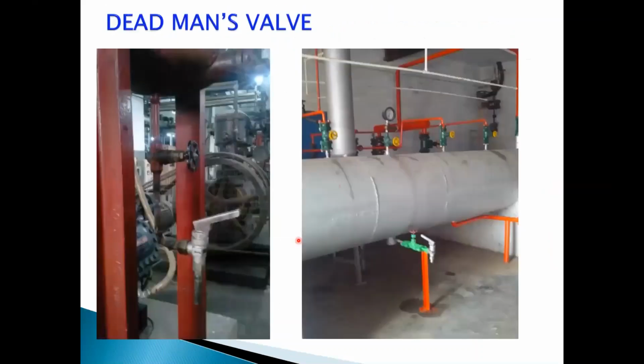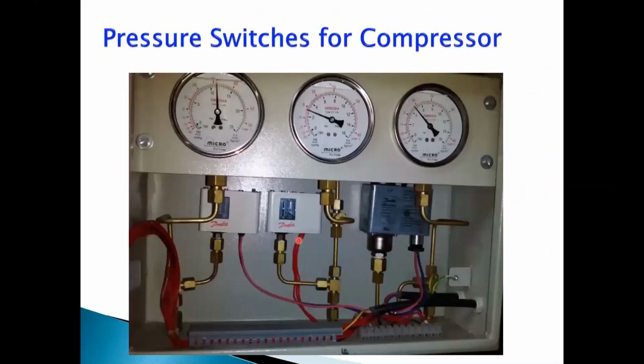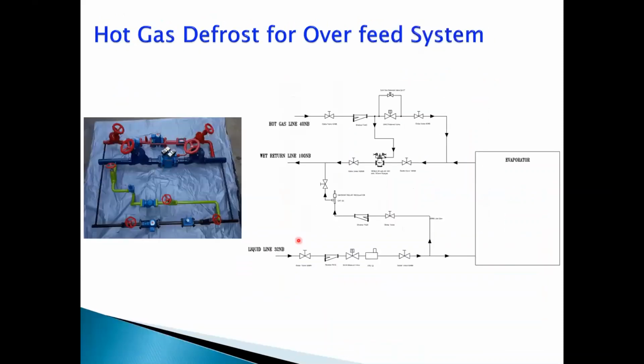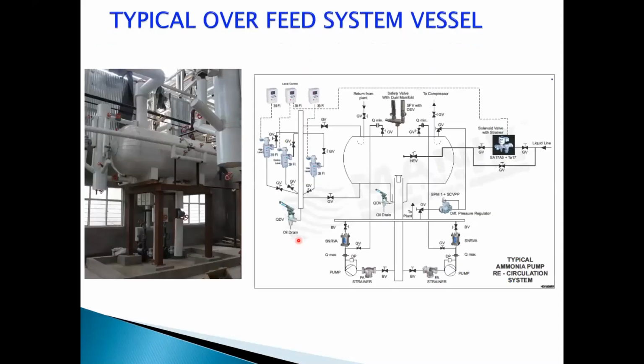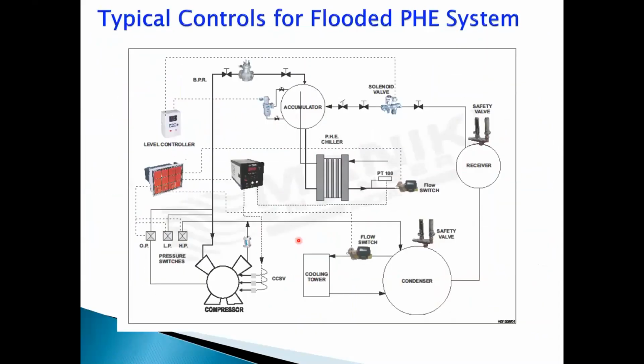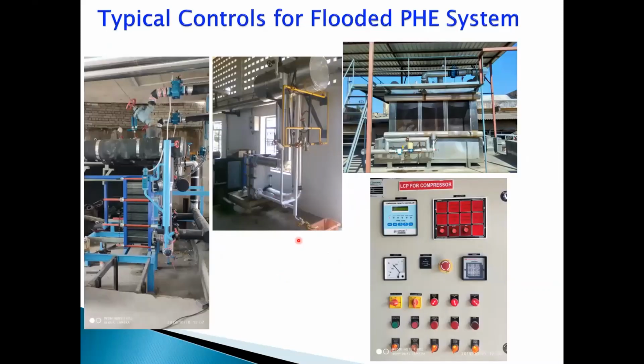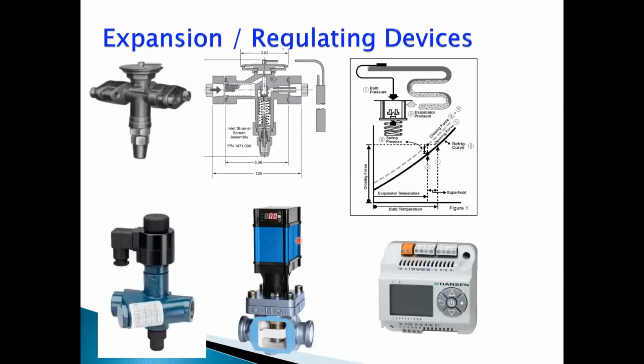Next, we have a question from Mr. Arun. Is any filtration required after the safety release valve before the ambient outlet? No, sir, no filtration is required because ammonia, as I told you, is a natural refrigerant. It does not have any atmospheric life. The atmospheric life of ammonia is 0. The moment it mixes into the atmosphere, it loses its toxicity. Typically, when ammonia is mixed with 20 times its volume of air, the toxicity becomes 0. When it is properly vented into the atmosphere, because ammonia is lighter than air, it will go above and mix into the atmosphere, so no filtration is required.